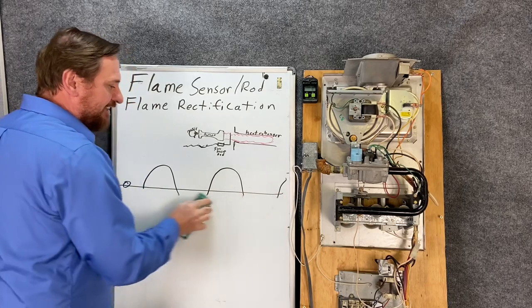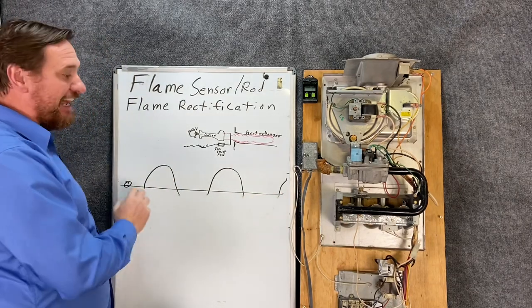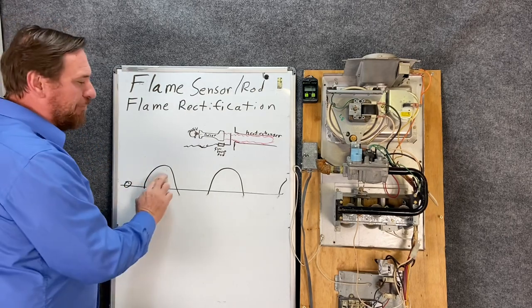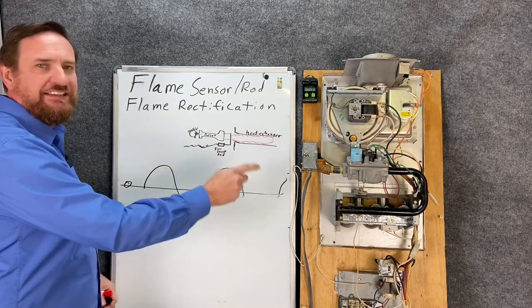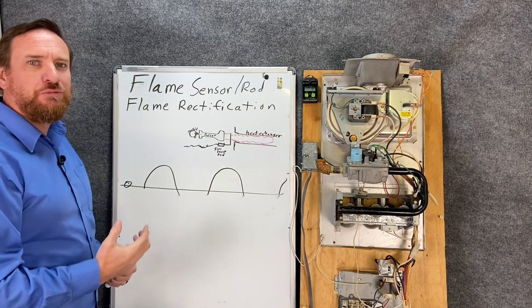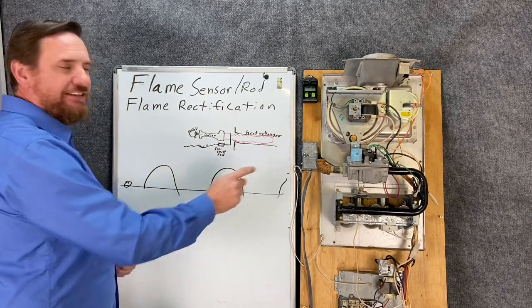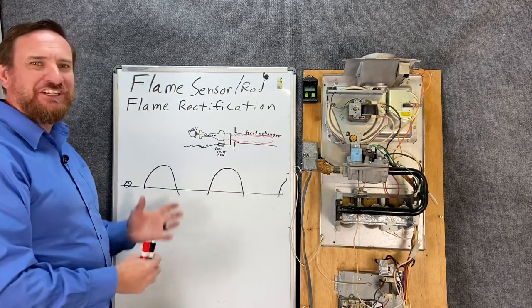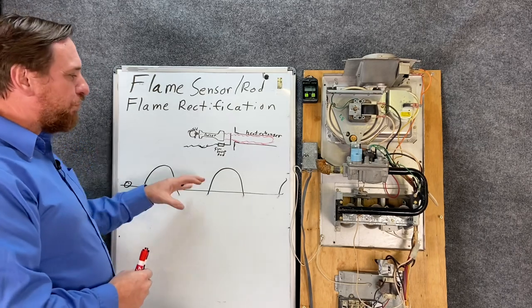So what we're going to actually do on flame rectification is erase our alternating current. So now if we see it's no longer an alternating current, which means positive, negative, it's now a DC current, but really it's not even a DC current, it's a pulsating DC current. So the control board is reading this pulsating DC current, and so that's how the control board knows that the flame is there. It's a very unique DC current. So I think that's absolutely awesome.